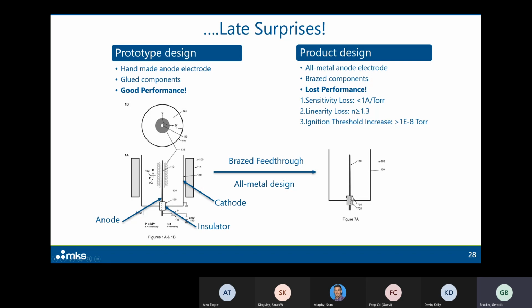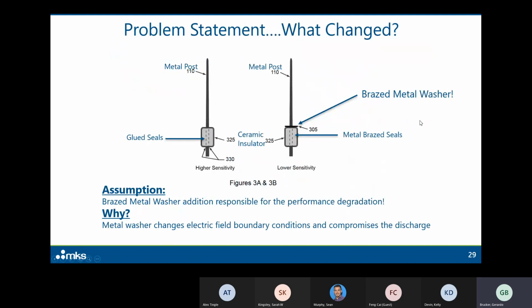When we put the braze feed-through in, thinking this is going to be the greatest thing since sliced bread, suddenly we lost performance. Sensitivity went down, less than 1 amp per torr. We lost linearity. The N value started to go higher than 1.3, and our ignition threshold became really bad. We were scratching our heads. What's going on, right? We tried a bunch of different things. We tried material changes, different designs for the feed-through and so on. And in the end, it really became apparent that there was something much more subtle going on.